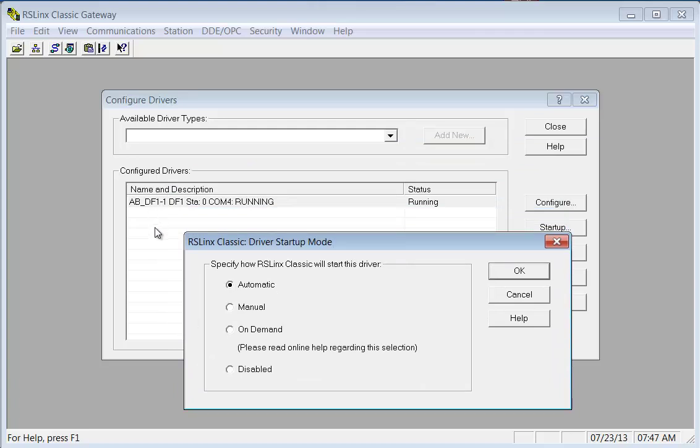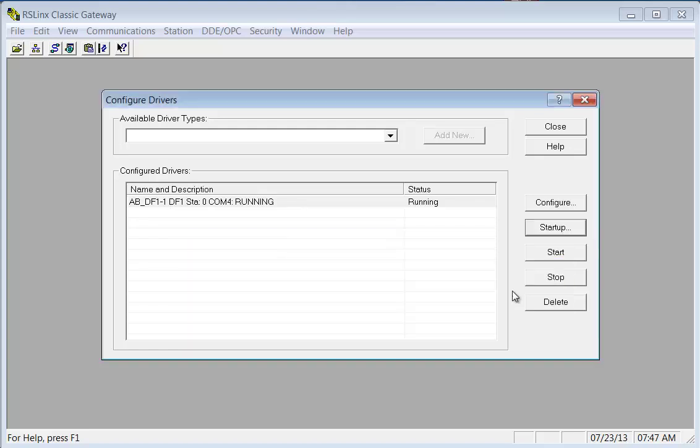Let's say that one of your customers is the widget company. Instead of letting it be ABDF1, you would let it be widget company DF1 or Monsanto DF1. And you can create all these uniquely configured DF1 drivers for all these different either process lines or companies. Then you change this to manual and then you select the one you want and start it. Okay, so there's a start button, a stop button. So if you had ten of these DF1 drivers here, they'd all be stopped. You'd go in and select one and hit start and away you go. So that's another little thing that we covered somewhat.